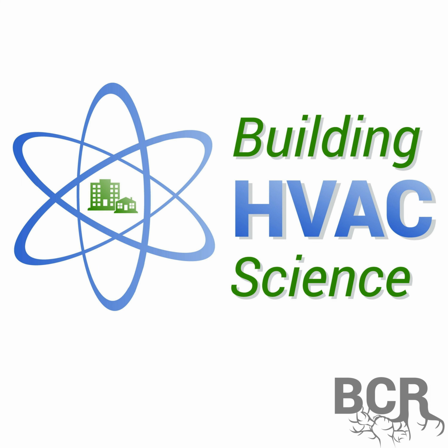So breaking this down, a duct blaster is a device typically used for measuring air leakage in ducts. There are a couple brands in the market, Retrotec and the Energy Conservatory, and you'll also hear of it being called a duct tester. Prices for this setup are around the $2,300 range at this point. Now that's pretty steep, but you've got to remember, like a lot of things, accuracy has its price. This kind of equipment will deliver superior accuracy, and it's sort of a one-shot deal. You hook it up correctly, you make the measurement, and there's your number.